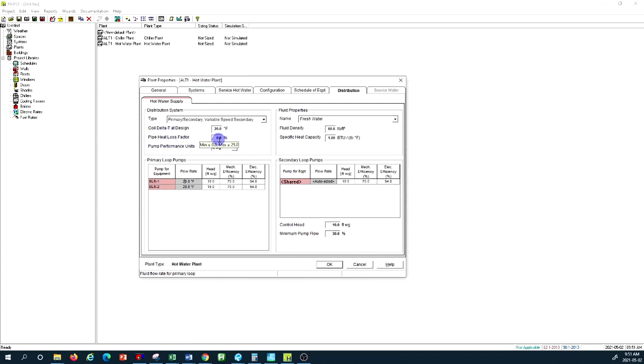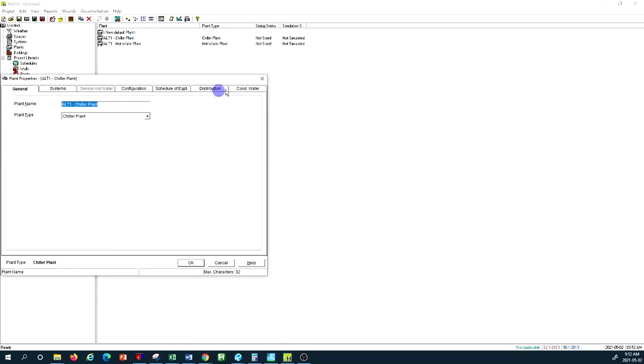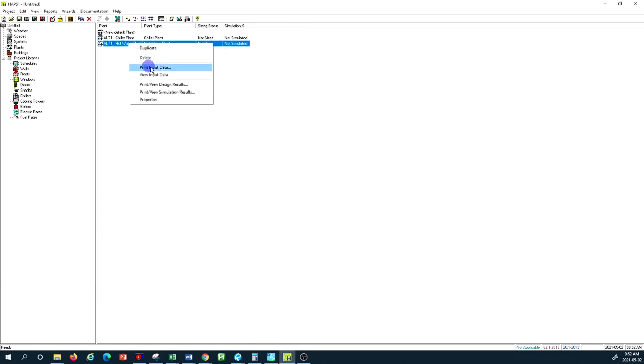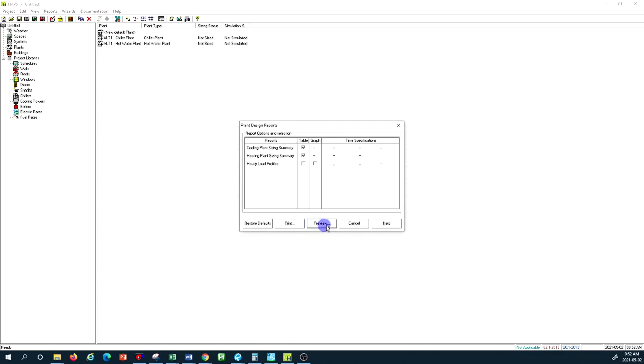At this level we have high-level calculations: three GPM per ton of load, so depending on the tonnage, three GPM of chilled water is dedicated to it. For the boiler, I use the heat capacity equation: Q = 500 × ΔT × GPM. With one boiler at 967,700 BTU/hr capacity, dividing by 500 × 20°F gives 96.77 GPM, which I round to 97 GPM per boiler, for a total of 194 GPM for both boilers.